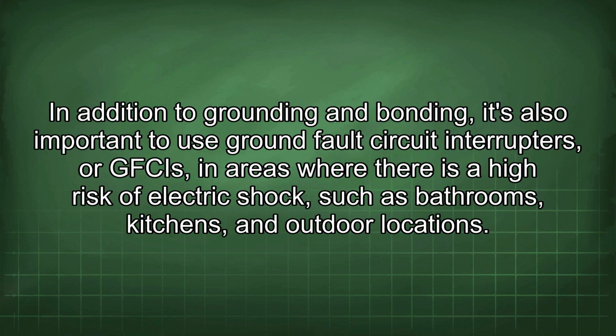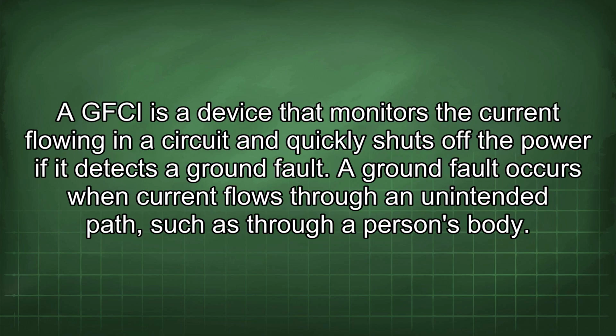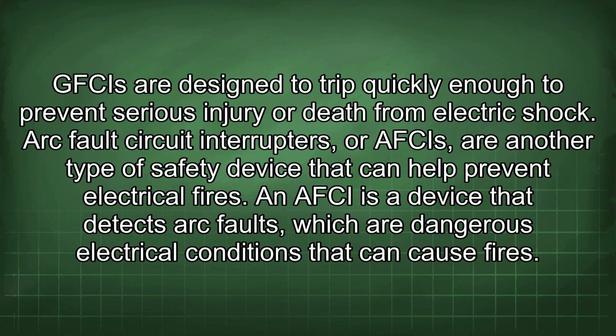In addition to grounding and bonding, it's also important to use ground fault circuit interrupters, or GFCIs, in areas where there is a high risk of electric shock, such as bathrooms, kitchens, and outdoor locations. A GFCI is a device that monitors the current flowing in a circuit and quickly shuts off the power if it detects a ground fault. A ground fault occurs when current flows through an unintended path, such as through a person's body. GFCIs are designed to trip quickly enough to prevent serious injury or death from electric shock.